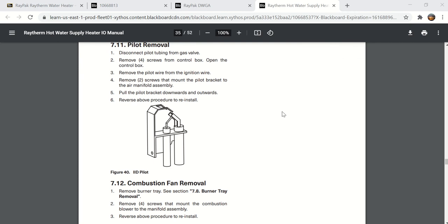Okay, further on in the RayPak manual here, you'll see a picture of the pilot assembly, and I'm going to go over a little bit about the Honeywell ignition control and some of the differences in different models. But this one here, you have the actual spark igniter, and it's sparking to this hood.